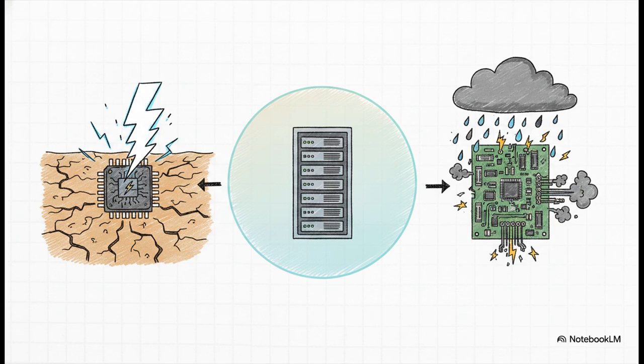Because of this, automated dampers will instantly slam shut and cancel the free cooling if the humidity steps even slightly outside that strict 20 to 80% safe zone.